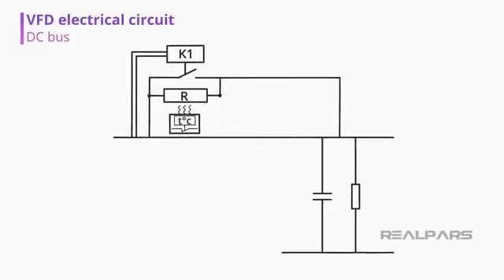When we energize our VFD and the bank of capacitors is not yet charged, the capacitors start to charge by the resistors. Once the VFD controls identify that the DC link is fully charged, it will then close the contact, becoming the path of least resistance for the electric current.